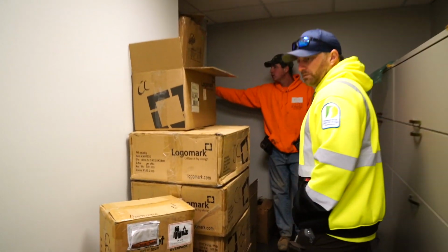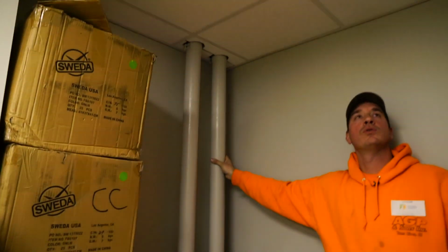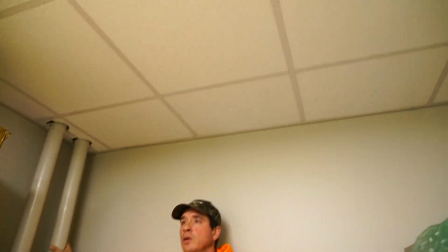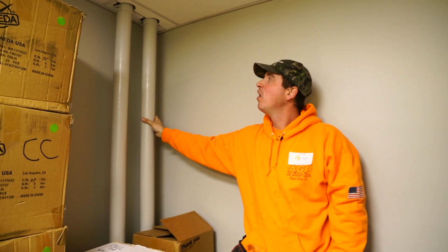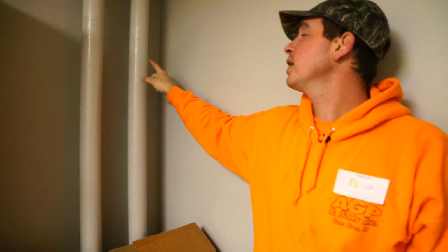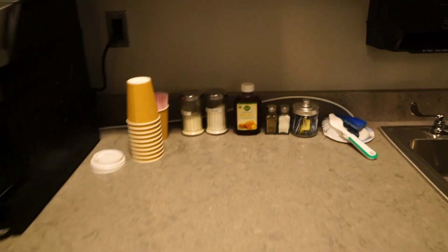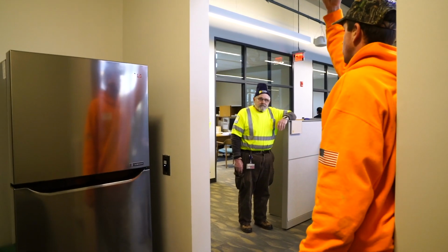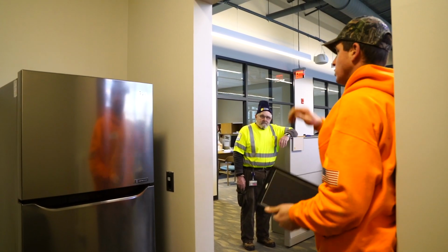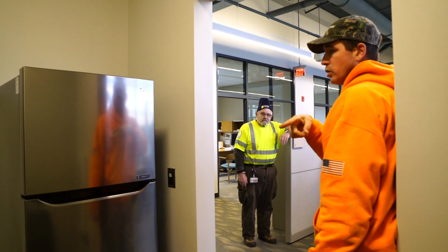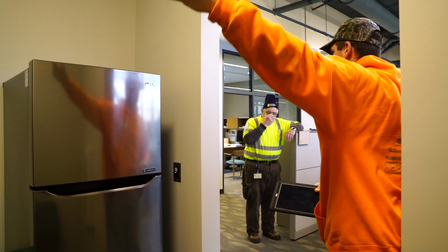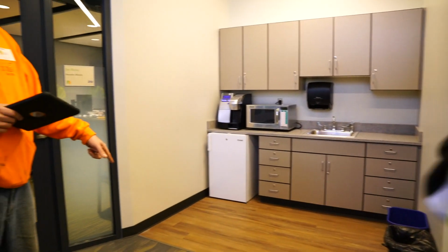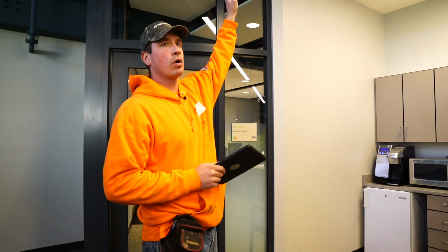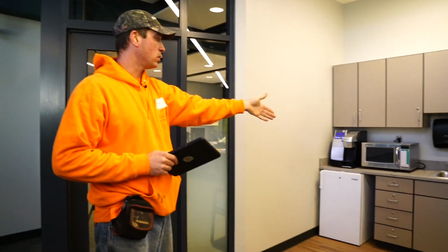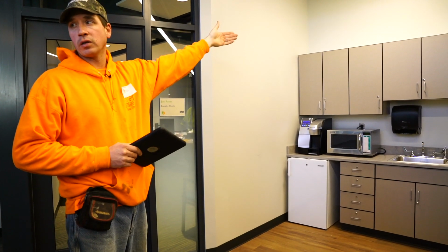So these are them over here. Like I said, and these 2 roof drains are overhead right here. All right. If I had to take a pretty good educated guess, this is my overflow and this was my main one. Kitchenette, if you remember down in the mechanical room downstairs, over by where the hot water heater is, you have your duct chase where the ducts are going up. You have the 2 water lines going across. Those isolation valves are for this sink. You'll see it's the only 2 water lines that go up with the ducts. The duct shaft is right on the other side of this wall. That's for that. The HR area we were in, where I said the valves are overhead in those 2 offices, that feeds the kitchenette sink and the bathroom, which is right on the other side of this wall.